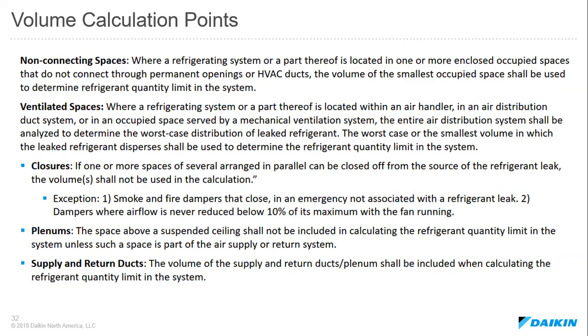So non-connecting spaces are spaces where a refrigerant system is located in one or more enclosed occupied spaces that do not connect. That happens quite a bit as we look at a building such as an office. We'll have a lot of enclosed occupied spaces. There also are ventilated spaces where a refrigerant system can be located and might be served by an air handler or an air distribution system. And within ventilated spaces, there are 3 other space classifications.